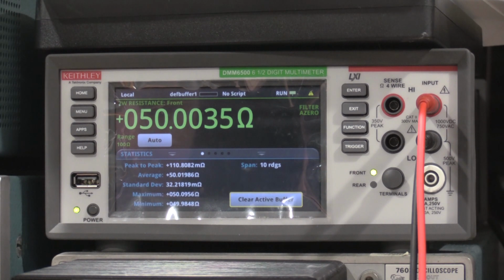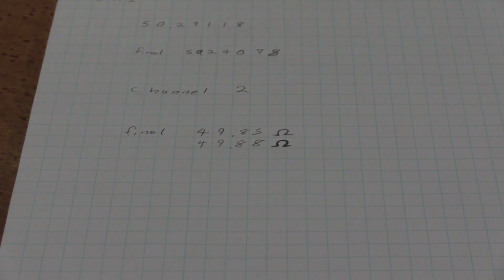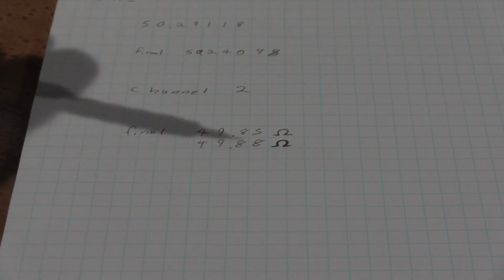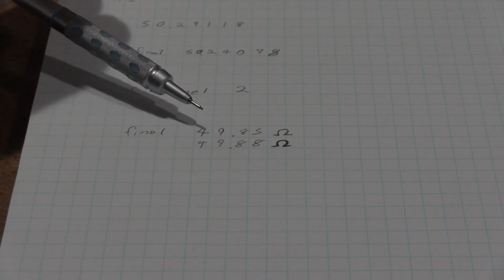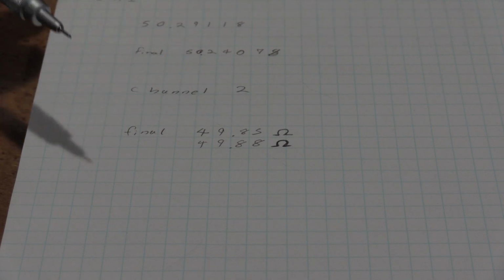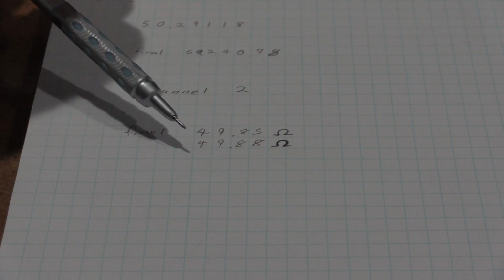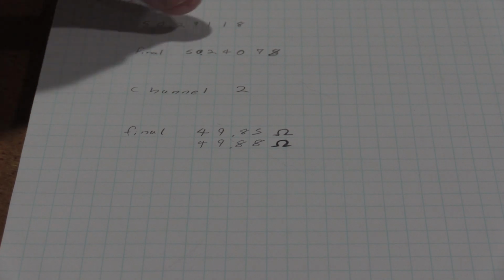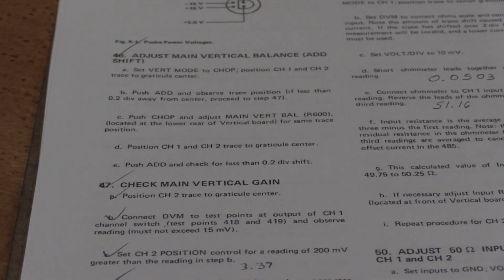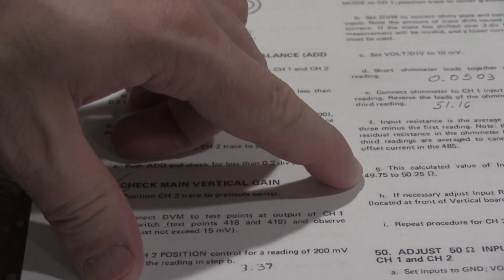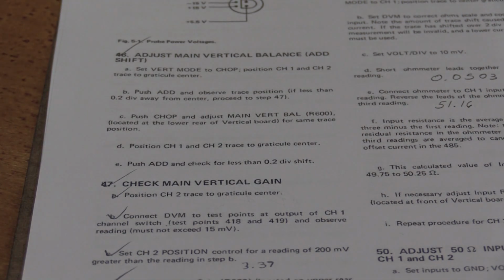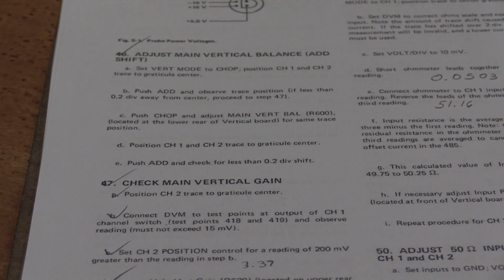I'm going to quit moving around in the lab. I'm going to run this again, and then I will bring you guys back. Okay, both of them were out of adjustment, and I had to do both channels. My finals ended up with channel 1 being 49.85 ohms, and my final on channel 2 was 49.88. And there's a very narrow window, 49.75 to 50.25 ohm for that adjustment, but we got it, so we're on to step 50.